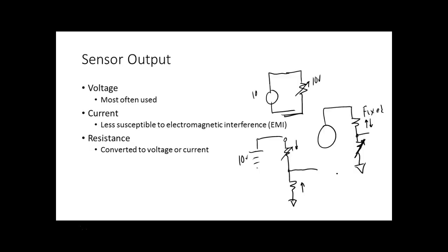What does the sensor do? So temperature sensors, we have what we call negative temperature coefficients and positive. Negative means their resistance goes down when the temperature of the measure goes up. The other one, a positive temperature coefficient, a PTC temperature sensor, means this resistance would go up when the temperature goes up. Now, the ones we have, I think those are NTCs, or negative temperature coefficients.